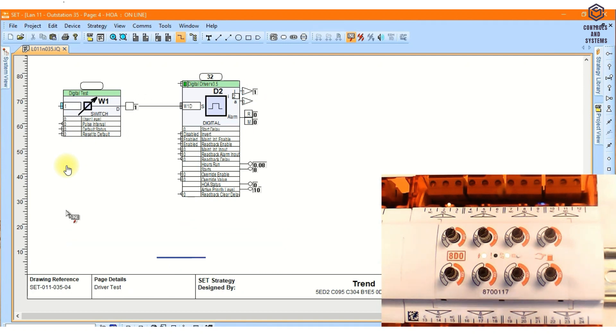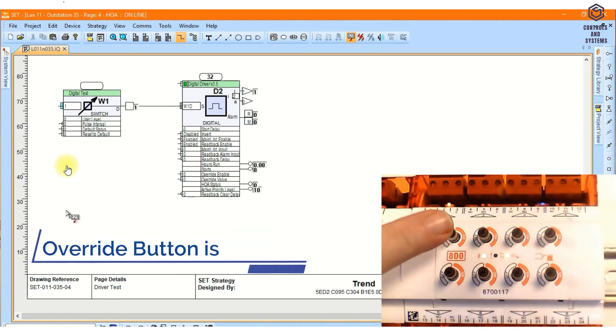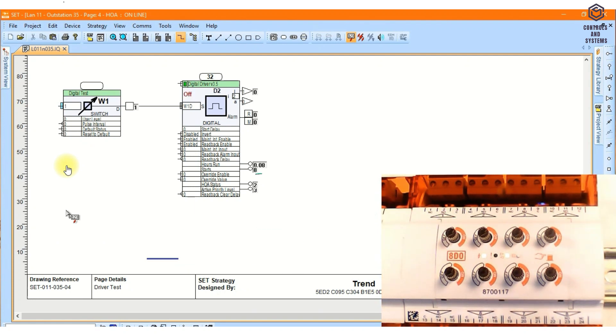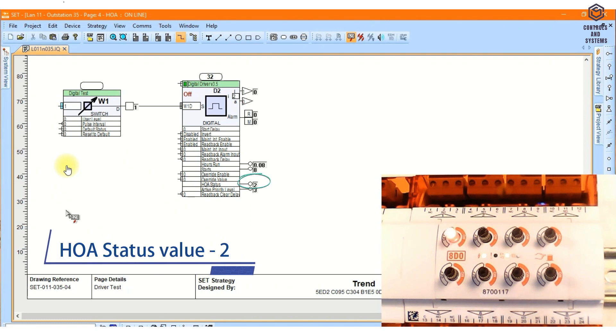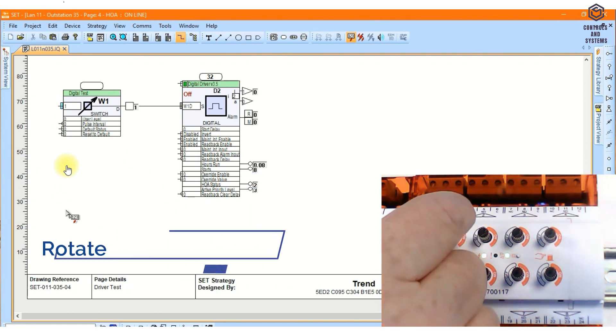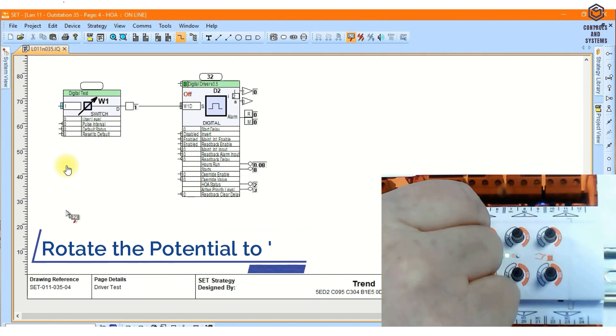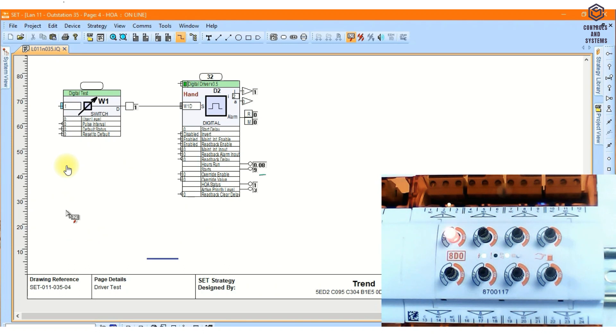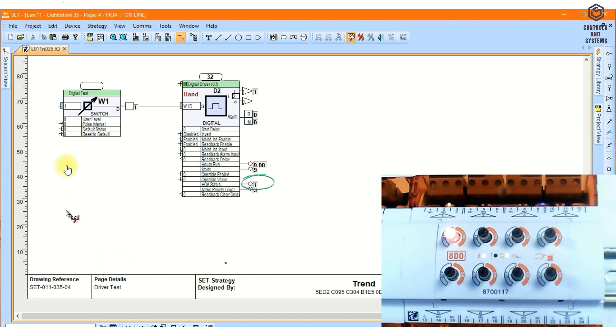If the override button is pressed, the LED on the output module will flash, and the HOA status will be shown at 2. Rotate the potentiometer to the on state, the digital driver will switch on and show the hand mode, and then the HOA status is shown at 1.